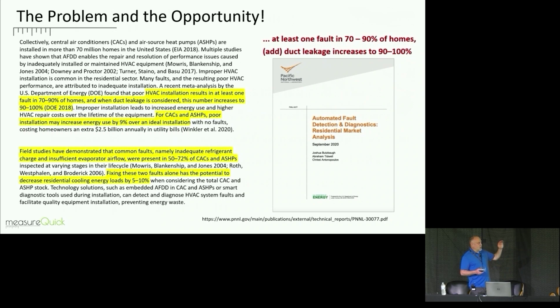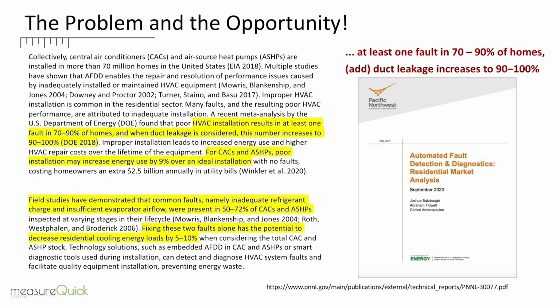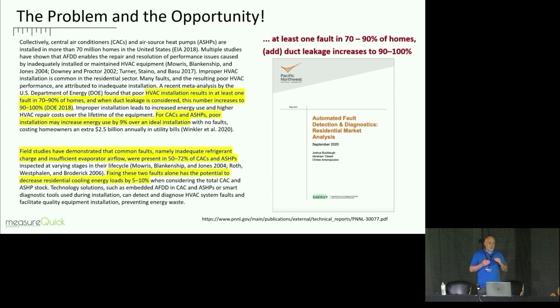Now the challenge we've got as an industry overall, and this is a huge opportunity right now, is that you have at least one fault in 70 to 90% of systems. So I want you to stop and think about this for a minute. And if you include duct leakage, it goes up to 90 to 100%. So 7 out of 10 to 10 out of 10 systems you go out to today have at least one fault. Most of them have multiple faults, right?